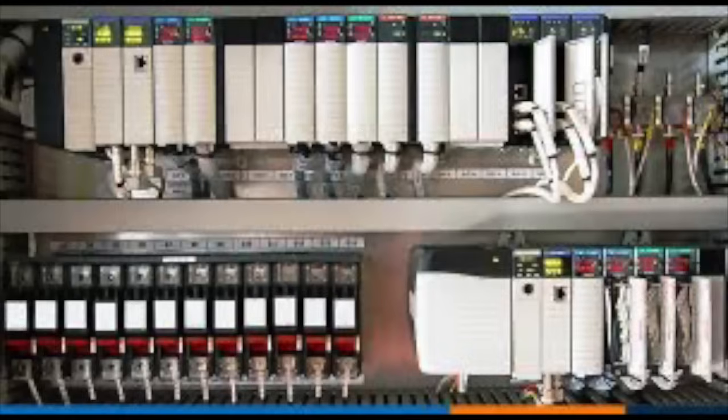So it would come home, and then right when that platen brake was basically instructed to come up, it wouldn't, because the logic would react faster than the mechanics could. So it would just come home and then just drift about 3 feet past that home position. And honestly, I think that was the year the ride was new, and he caused days of downtime on that, because we started getting frustrated and we started replacing valves and components and wiring and PLC card controllers and all sorts of other stuff, and we were trying to get ahead of that. Couldn't figure out what it was, and I finally caught it.